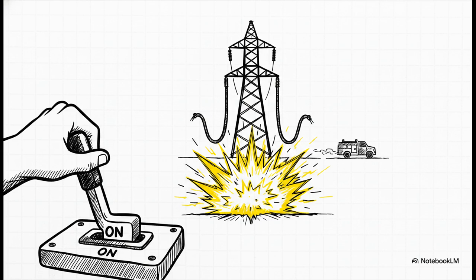But you know, even blazing fast communication can't always solve human error. Consider this really scary edge case. Let's say a maintenance crew powers down a line and attaches heavy grounding cables so they can do some safe repair work. They finish up, pack up the trucks, but oops, they accidentally forget to remove those grounding cables. Then, the operator back at the control center throws the switch to turn the power back on, literally closing the breaker directly into a massive three-phase short circuit.